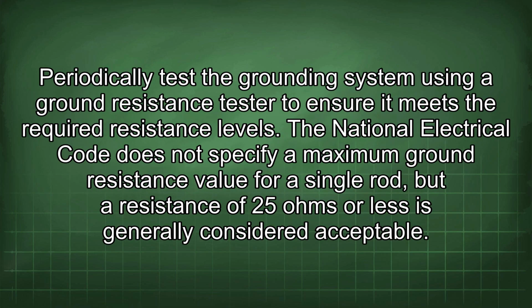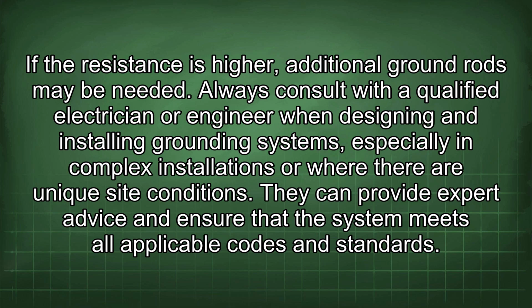Periodically test the grounding system using a ground resistance tester to ensure it meets the required resistance levels. The National Electrical Code does not specify a maximum ground resistance value for a single rod, but a resistance of 25 ohms or less is generally considered acceptable. If the resistance is higher, additional ground rods may be needed.